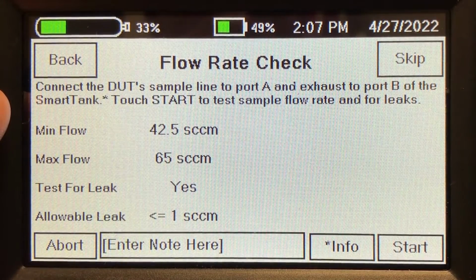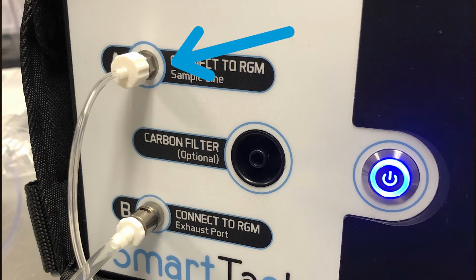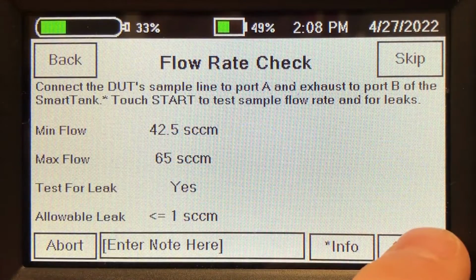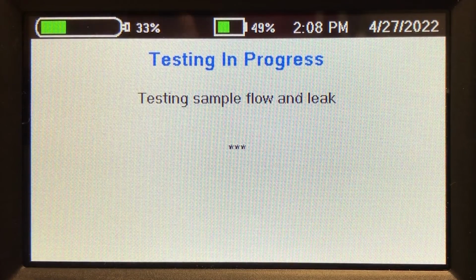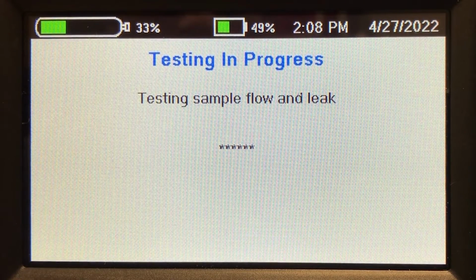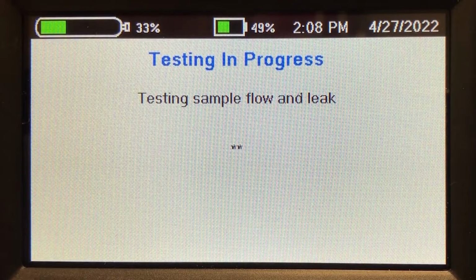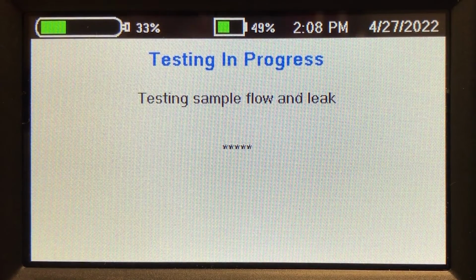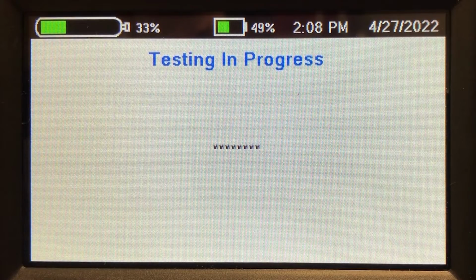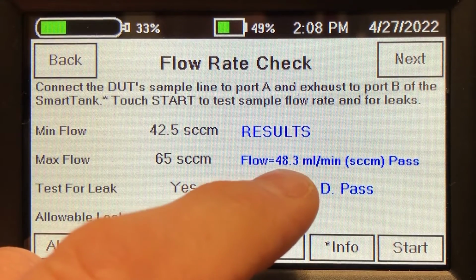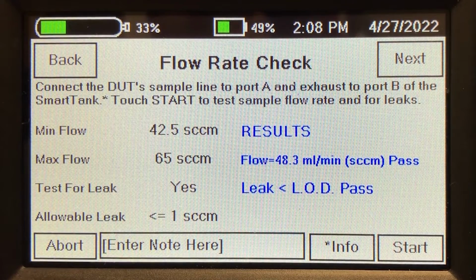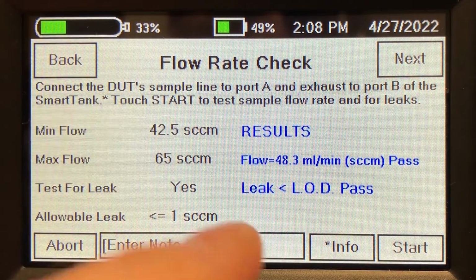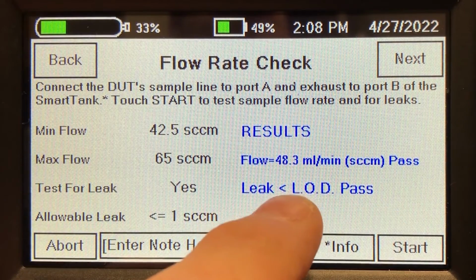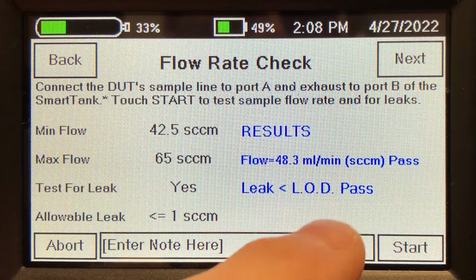Next test, we're going to connect the sample line up to port A on the smart tank and the exhaust of the extension module to port B on the smart tank. And then we just press start. The smart tank now is measuring the sample flow rate, and it's also going to switch an internal valve which allows it to directly measure any leaks inside the extension module that we're testing. So the flow was 48.3. The nominal setting for this device is 50, so it's pretty close and it's well within the pass criteria. It passed, there was no leak, or the leak was less than the limit of detection.